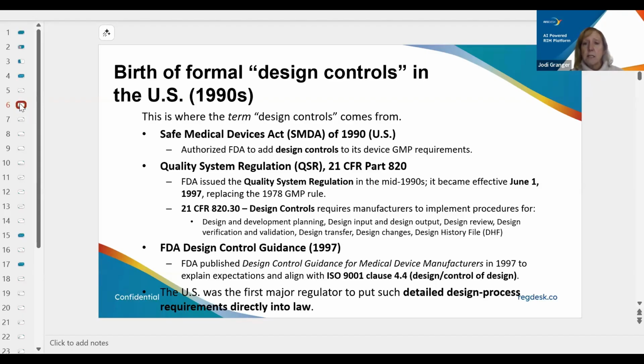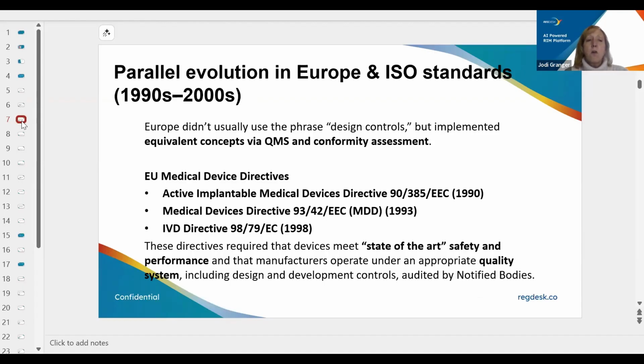So that design history file is a dynamic group of documents that basically show the life cycle of your product from beginning to end. So FDA did issue a design control guidance in 1997, and that was available to manufacturers. So although the US kind of kicked off that design control terminology, there was parallel evolution going on in Europe and the creation of ISO standards throughout the 90s and early 2000s. Europe does not use the term or the phrase design control, but they've implemented equivalent concepts through their quality management system and conformity assessment processes.